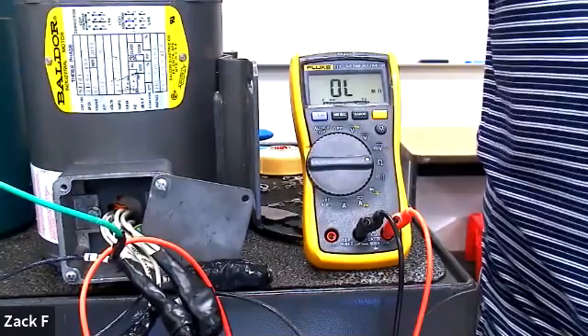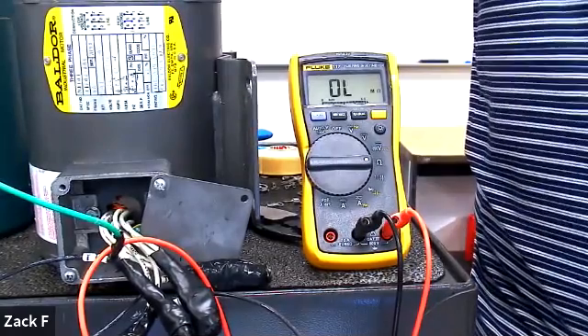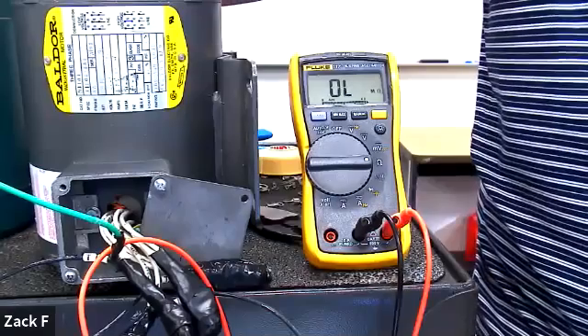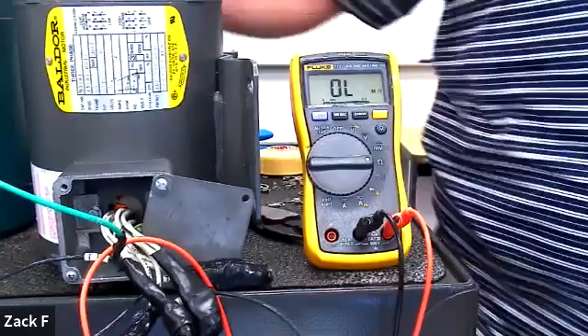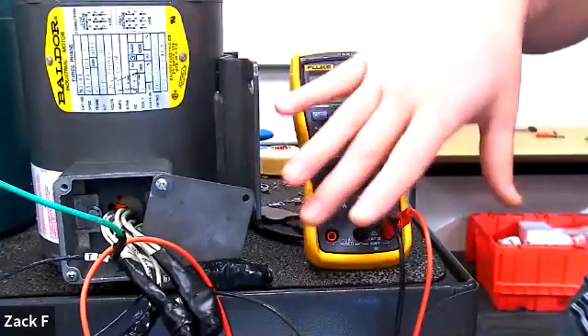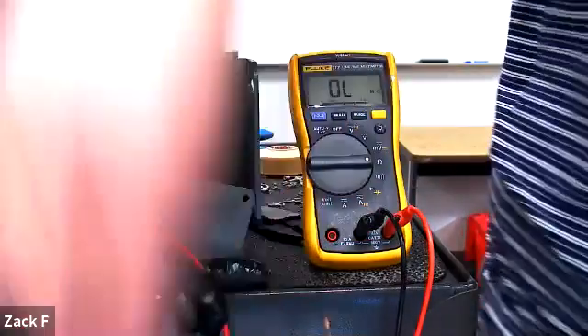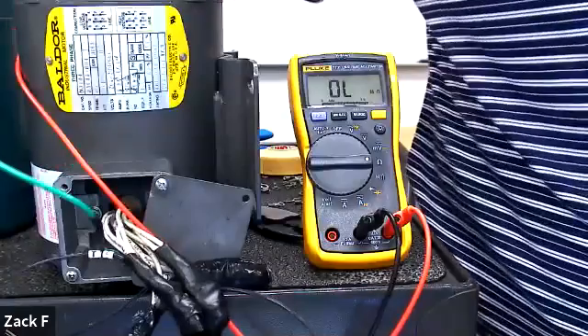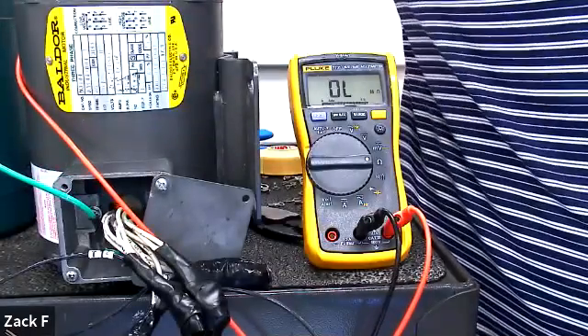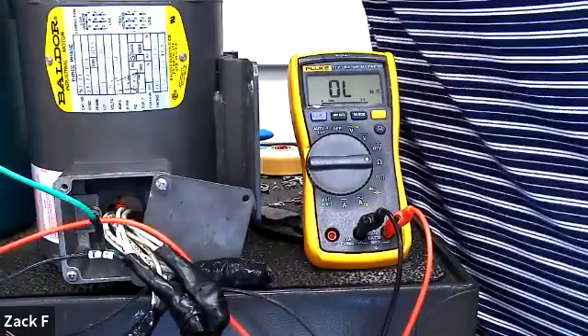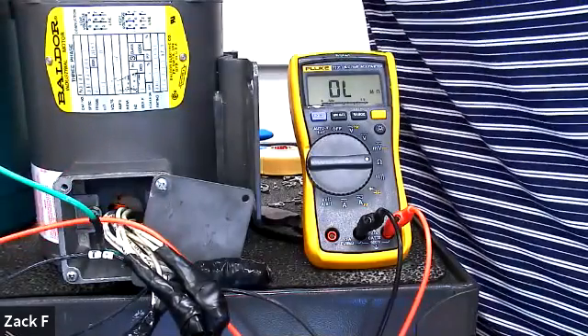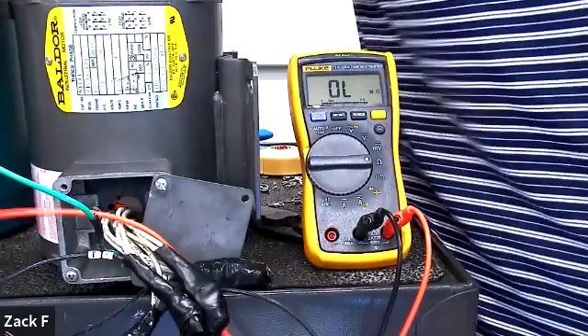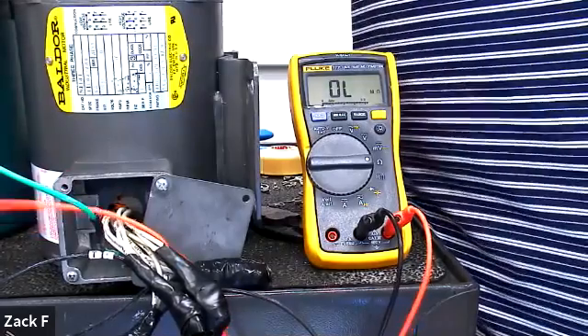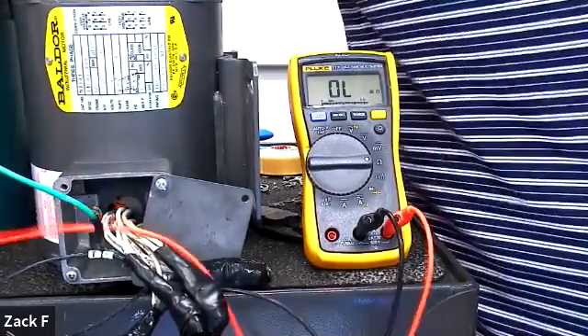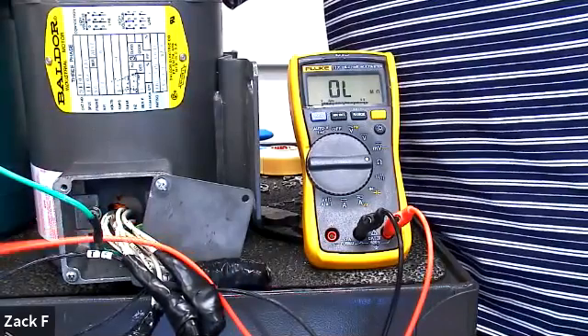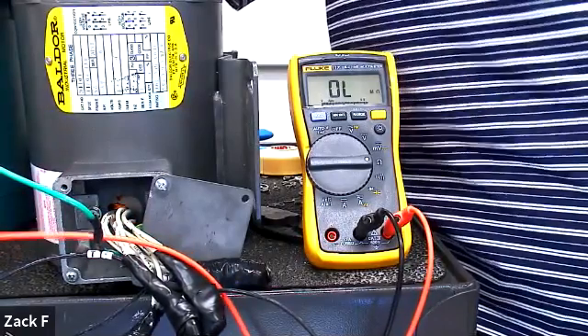There is no ground for these. I really should probably provide you with a ground, but for the purpose of these, you're not going to test the ground with your meter. You're going to use the megger, but a ground on this would be anywhere on the casing, right? Because you're assuming that whoever the electrician that hooked this up is a good electrician and grounded the casing. So if a winding does burn up and ends up touching the casing, it'll trip a breaker or trip the overloads.